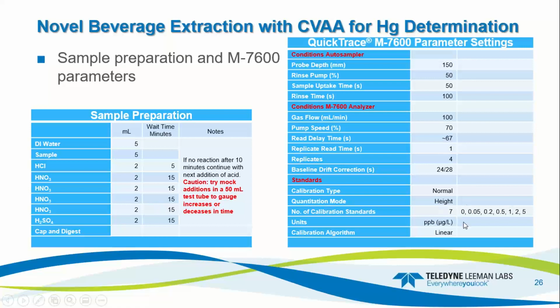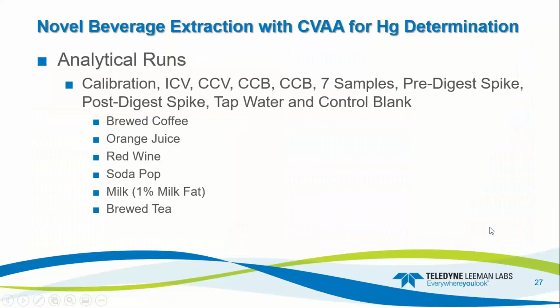Calibration is linear. I use quantitation mode of peak height. This system gives you the option of doing peak area and or peak height. Just depends on how fast you want to run it. And then my calibrations, again, were 7 calibrations, PPB level and linear. So the analytical runs I performed: calibration, ICV, CCV, CCB, CCB, 7 samples, pre-digest spike, post-digest spike, tap water, and control blank.